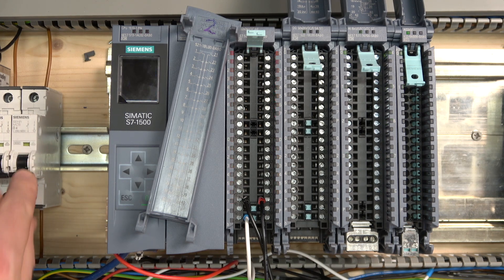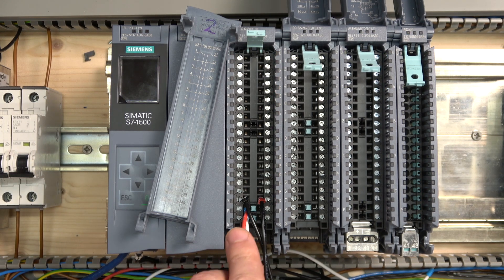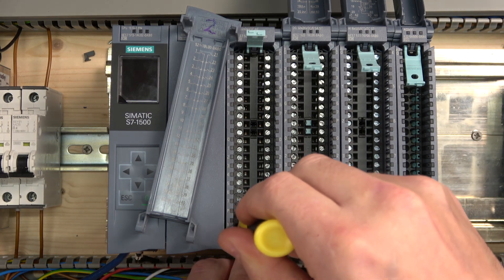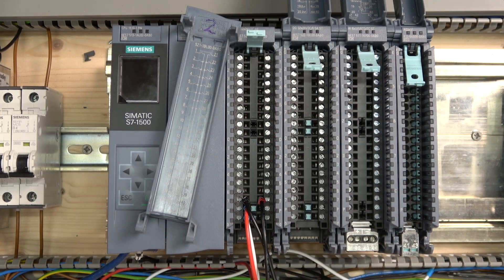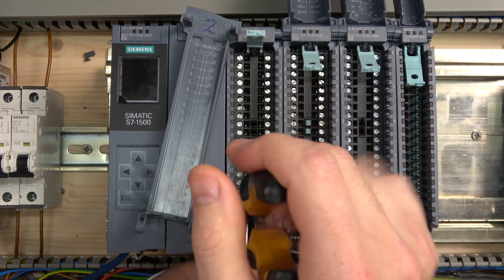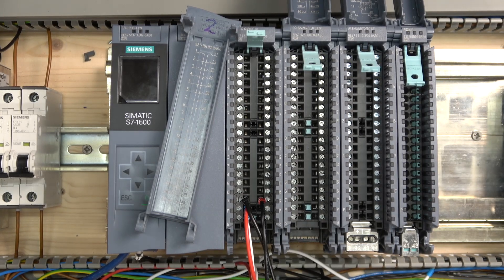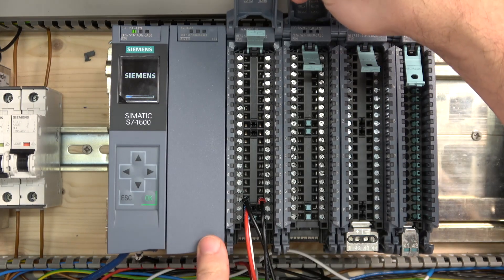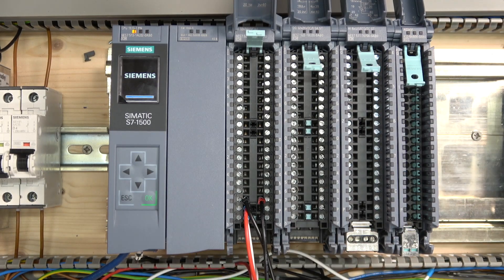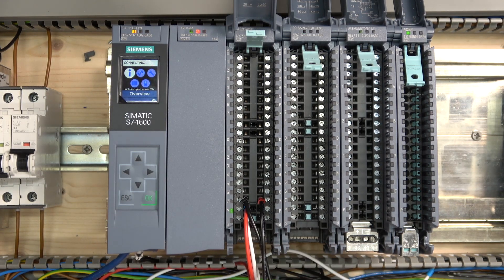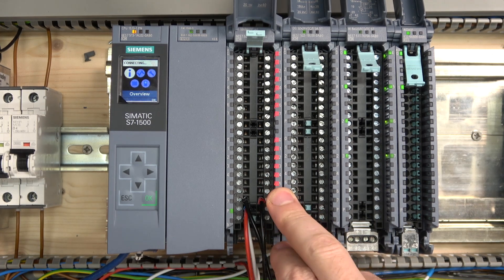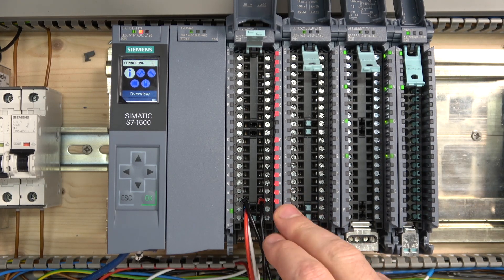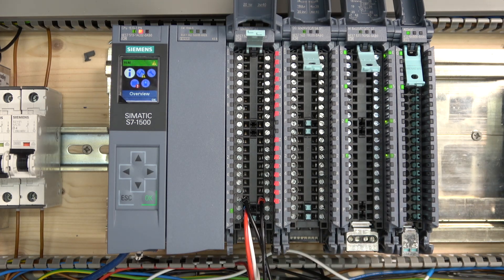Let me just depower, put the power back in and show you what happens if one side, if you're using two separate power supplies. What we're going to do, these pins are fairly easily pulled out. So I'm just going to pull this plus one out for now, and let's start it up. Put this guy back on, we no longer need it, hopefully we already understand how the system works. And if all goes well, one side is going to work, another one is not. As you can see, one side now shows it's dead, it says the wire is broken, I don't have 24 volt DC supply. The system is not working, you need to go investigate.